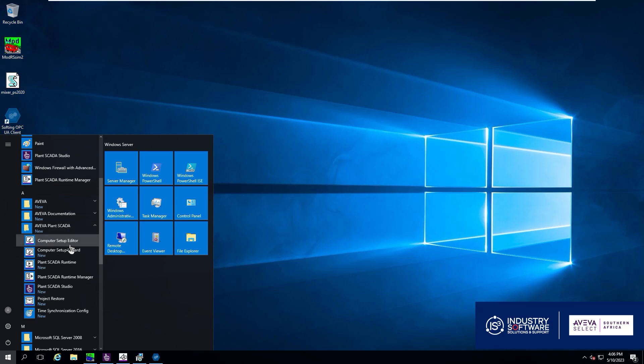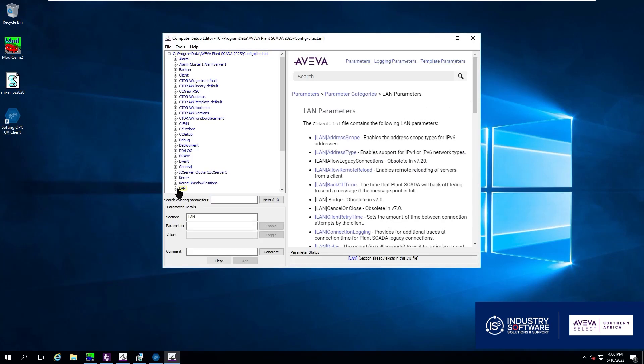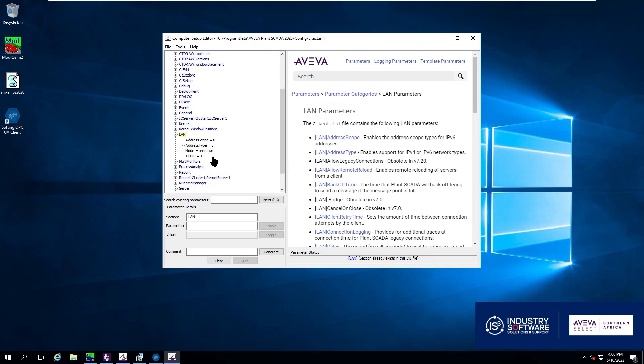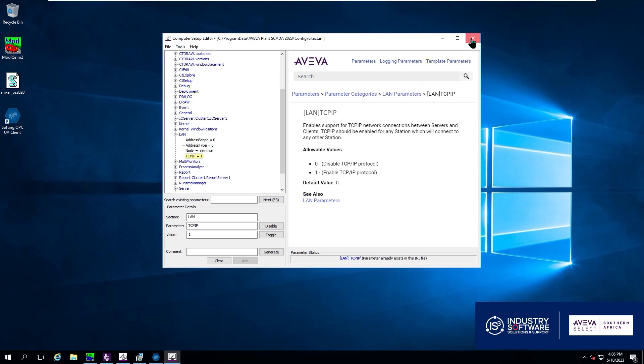So we go and we open up our setup editor and we pull up the LAN parameter category and we check our TCP IP and if need be set to one. This will be your most common reason for your communication not working.